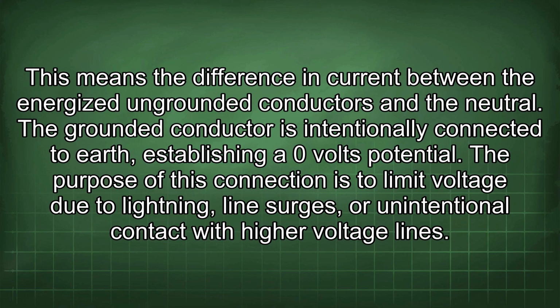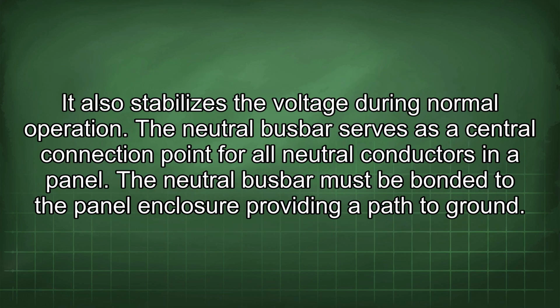The grounded conductor is intentionally connected to earth, establishing a 0 volts potential. The purpose of this connection is to limit voltage due to lightning, line surges, or unintentional contact with higher voltage lines. It also stabilizes the voltage during normal operation.